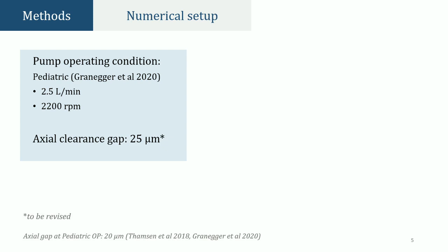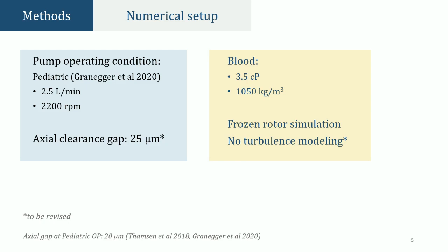We simulated this pump at 2 operating conditions, pediatric and adult, which we took from Granegger et al. 2020. However, in this presentation, I can only present the first half of this work. We fixed the axial clearance gap at 25 microns and used a frozen rotor simulation approach. At this stage, there is no turbulence modeling.